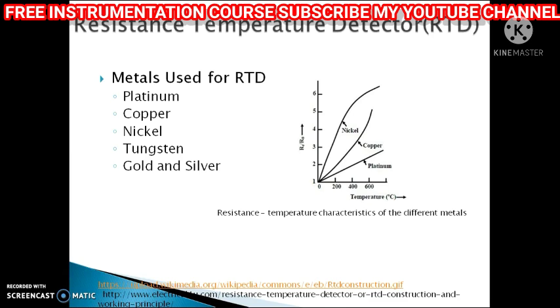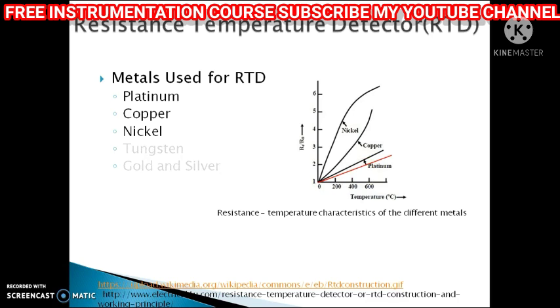Looking at the resistance-temperature characteristics, platinum has a very linear characteristic, whereas copper and nickel are completely nonlinear — that is why nickel RTDs have a very small range and are very cheap. Tungsten, represented by the red line, also has linear characteristics, but its purity is lesser than platinum and it is very brittle to work with. Gold and silver are two additional materials.